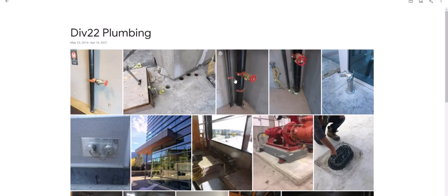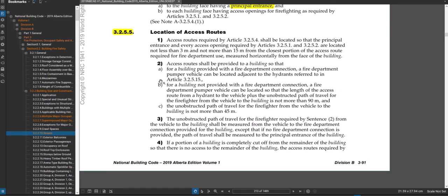What you'll find in a stairwell is the standpipe system with a hose connection, so the fire department can run up to the floor with the fire and connect their hose. There's another article in the code that determines whether you need a standpipe system and siamese connection. These articles also talk about fire hydrant distances — if you don't have a fire department connection, the fire hydrant can't be more than 90 meters from the building. This is important to consider when planning your site plan.